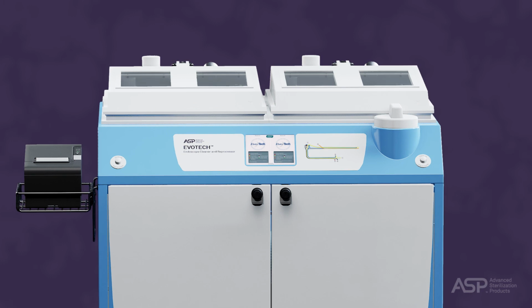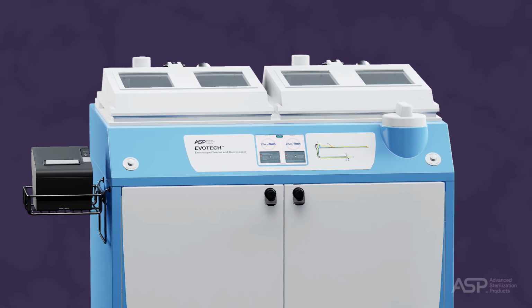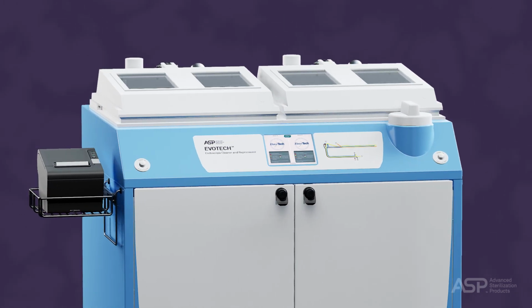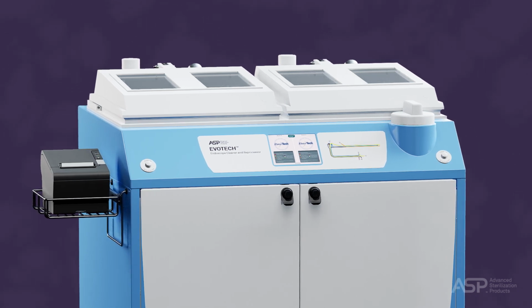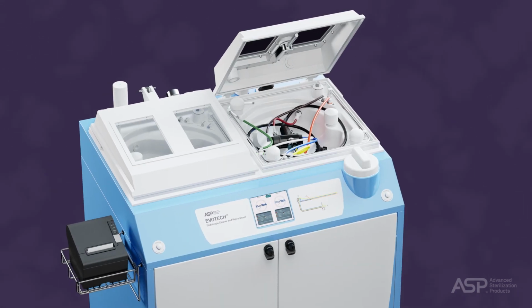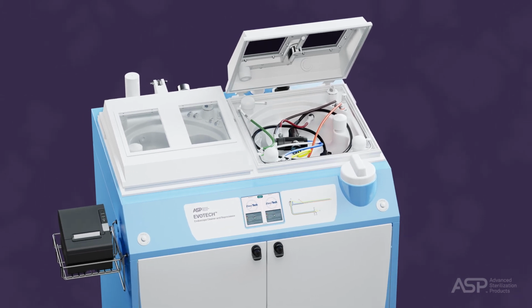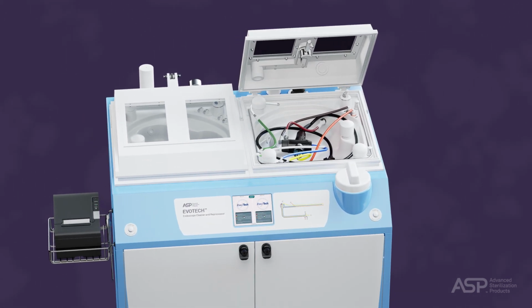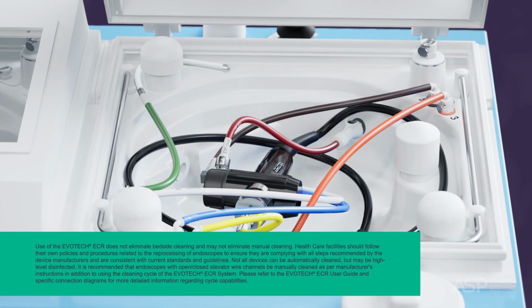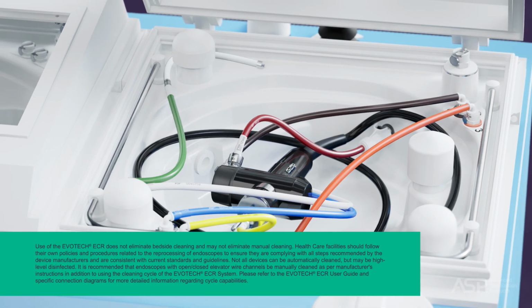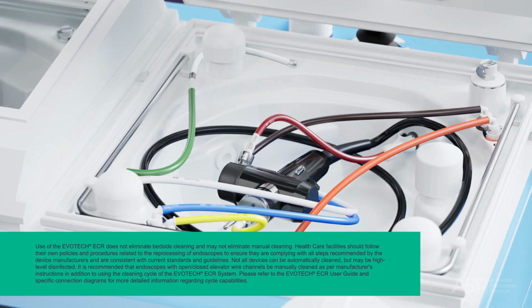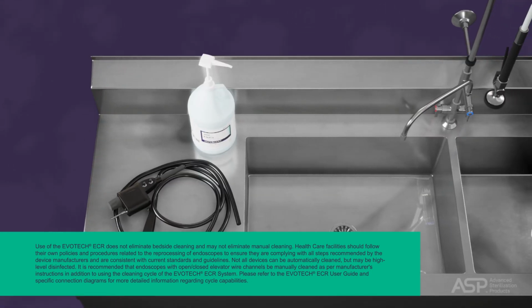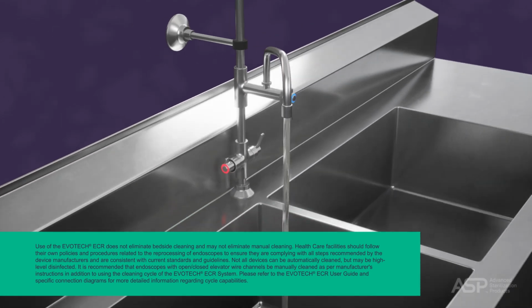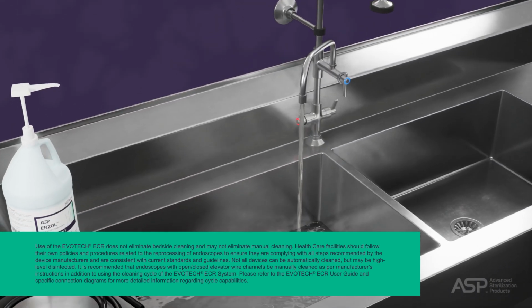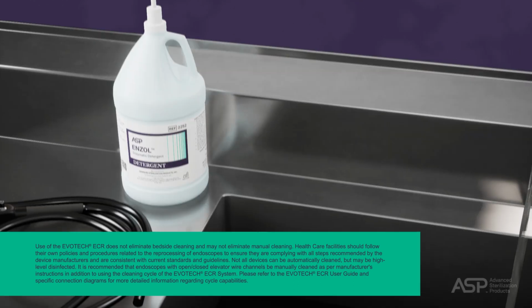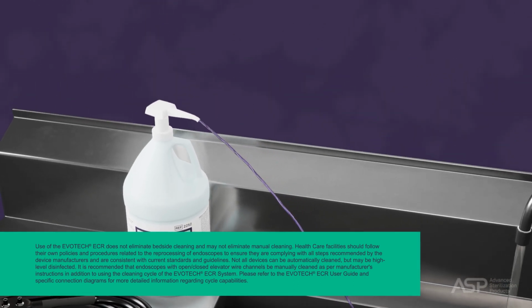The EVOTECH ECR has been cleared by the FDA to replace the manual cleaning process of the endoscope when selecting a cycle with a cleaning stage. However, it is the facility and department's decision to determine the extent of manual cleaning required prior to placing the endoscope in the EVOTECH ECR. Use of the EVOTECH ECR does not eliminate bedside cleaning and may not eliminate manual cleaning. Healthcare facilities should follow their own policies and procedures related to the reprocessing of endoscopes to ensure they are complying with all steps recommended by the device manufacturers and are consistent with current standards and guidelines.